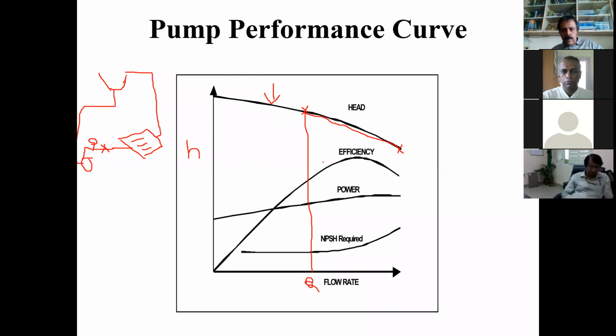The next curve, what you see is the efficiency. For various flow rates, we have this efficiency. And the efficiency curve, you see, it's quite unique again. You will find that the maximum efficiency of the pump occurs at one particular point, that is at this flow rate. So at this flow rate, you will get the maximum efficiency of the pump and against this head.